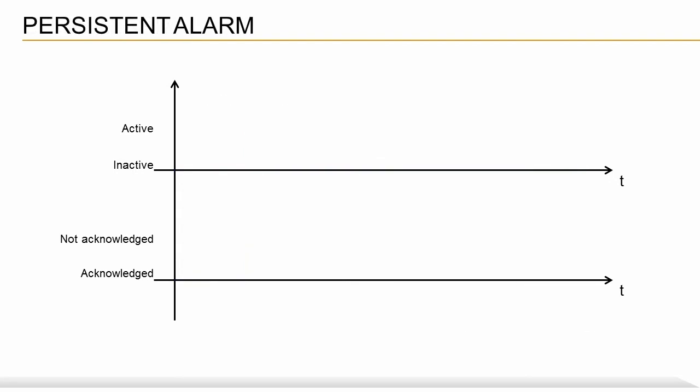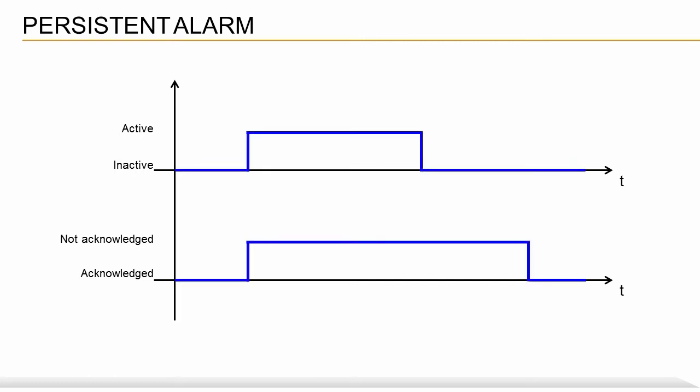Persistent alarms remain active until a certain condition is met, or until the state of an alarm changes. These alarms are set and reset manually. An example would be a temperature violation in a heating zone, where the alarm remains active until the temperature in the machine returns to normal, at which point it is reset via the application. The alarm can then be acknowledged via either the HMI application or the control application.